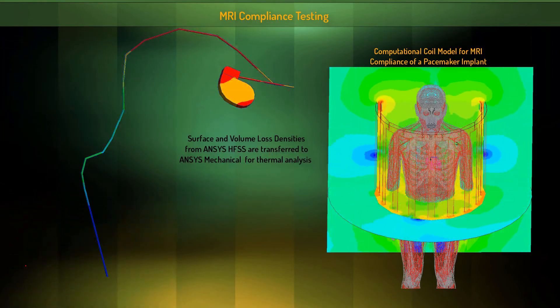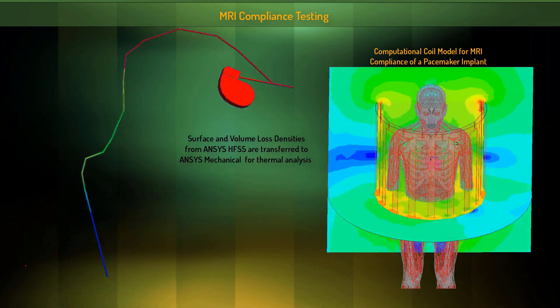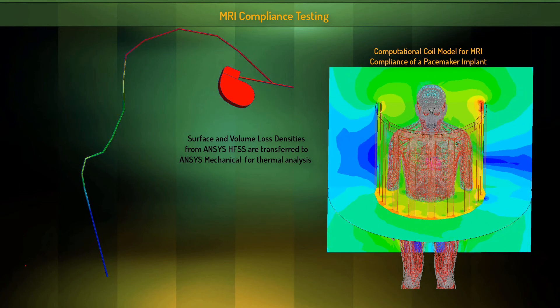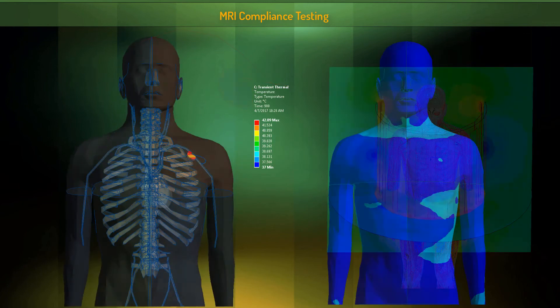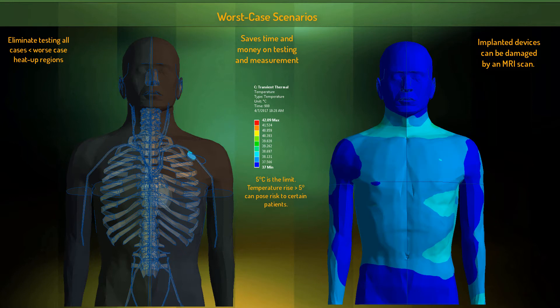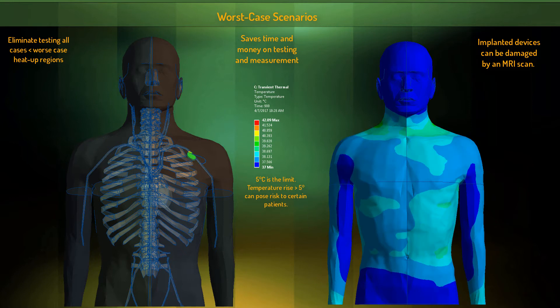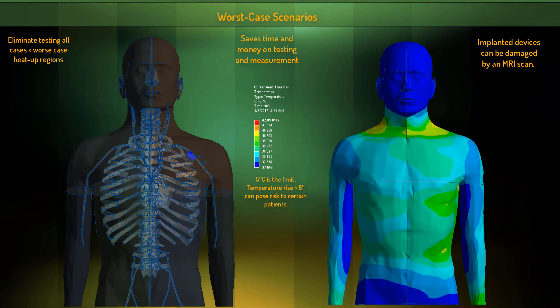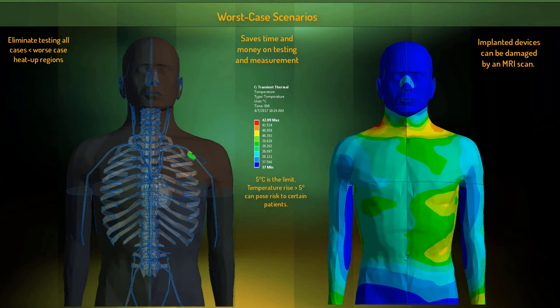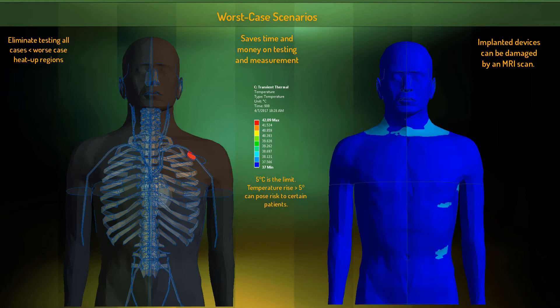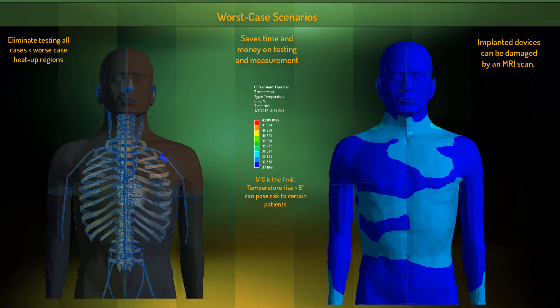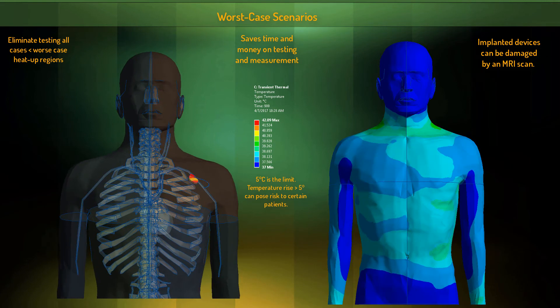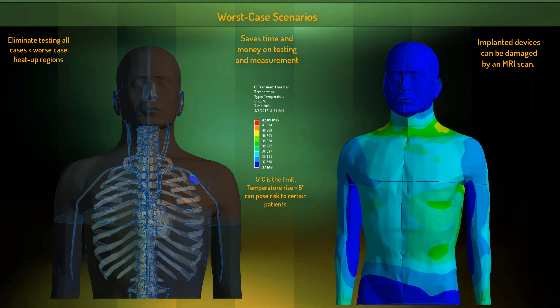One example is the creation of a standard computational coil model for MRI compliance of implanted devices. MRI compliance testing is a complex, multi-physics problem requiring time-consuming and costly measurement techniques. The FDA has determined that simulation can be used to identify worst-case scenarios to decrease the number of test points needed for submission.